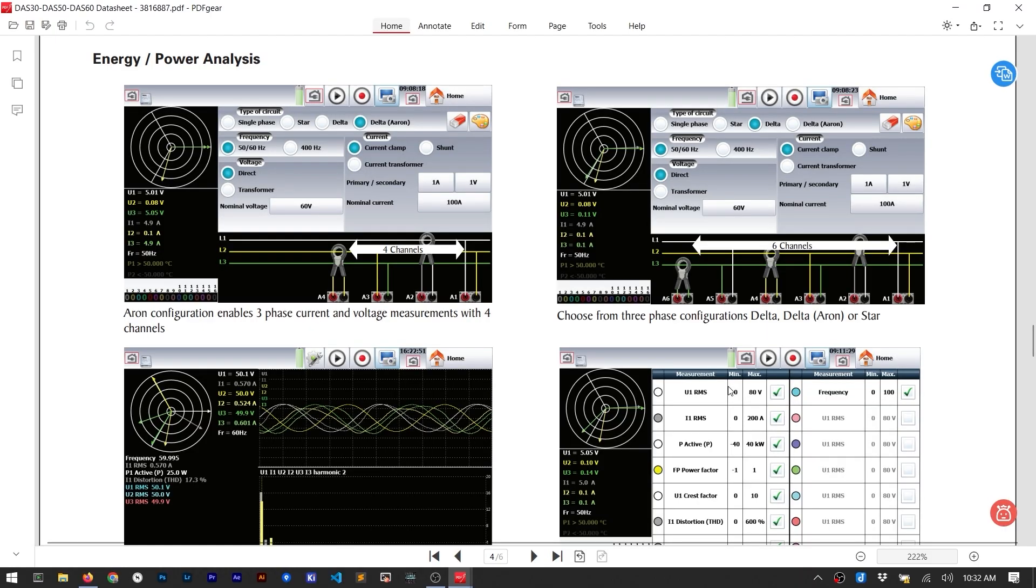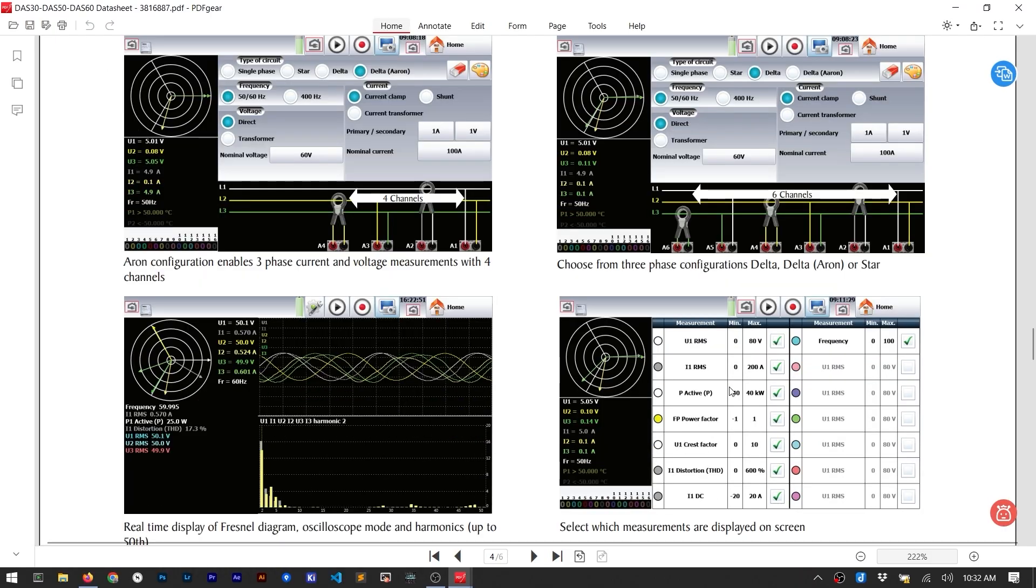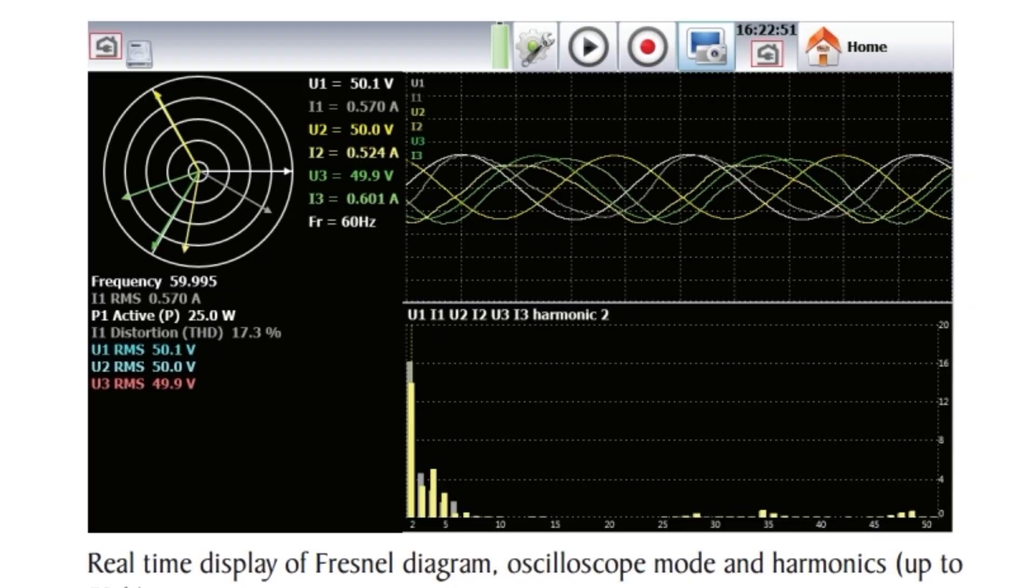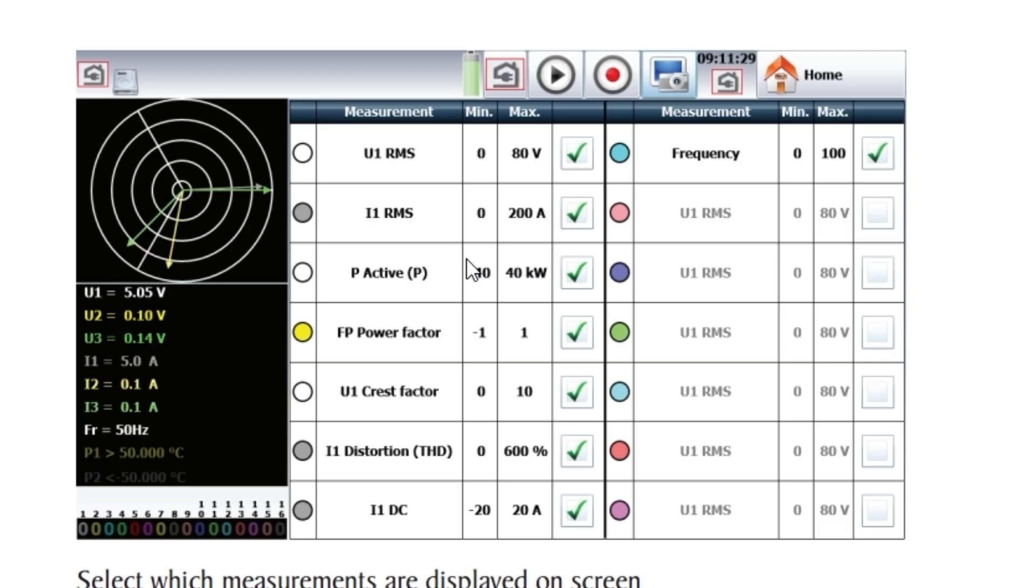You can also use a current clamp to make measurements, but I don't have one with banana connectors. If I did, then I could have made use of the power analyzer measurement. It allows you to measure single or three-phase power. You can see data in multiple displays. For example, you can view the harmonics as a graph, or make measurements like power factor and crest factor.